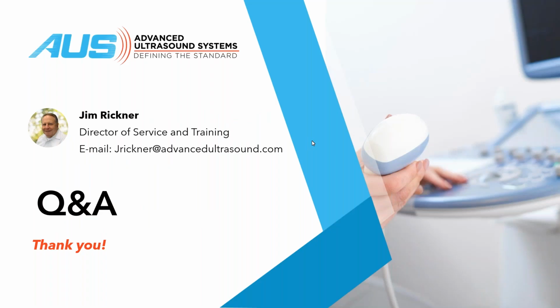Perfect. So how often would you recommend a practice test its ultrasound systems with a phantom, like monthly, quarterly, or only when they suspect an issue? Well, the reality is you should probably test it quarterly to semi-annually. All of our customers, we highly recommend semi-annual PMs that include image quality. The other time I recommend checking image quality is if you get a new probe. Let's say the probe got damaged, got dropped accidentally, and you got a new probe put in-house. When it gets put into service, you should immediately do an image quality test using a phantom on it and establish a baseline for that probe as it enters service at that facility.